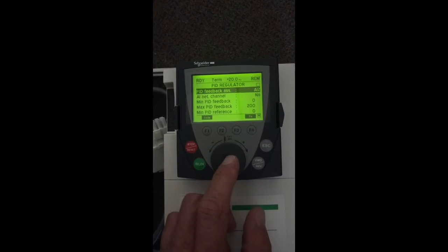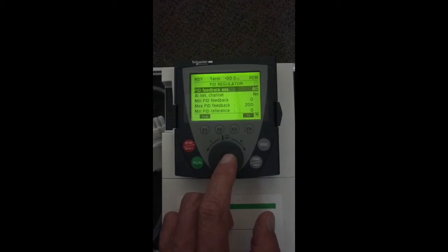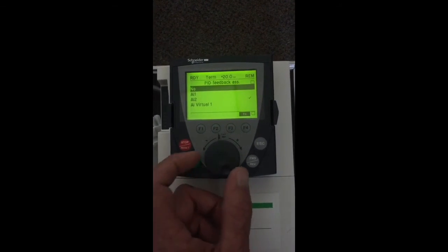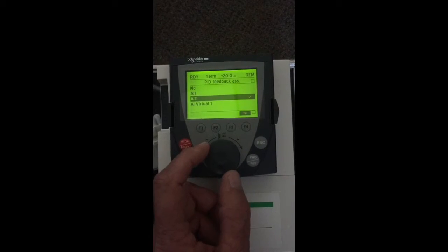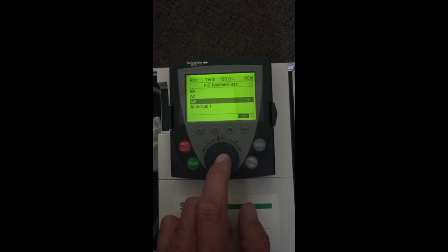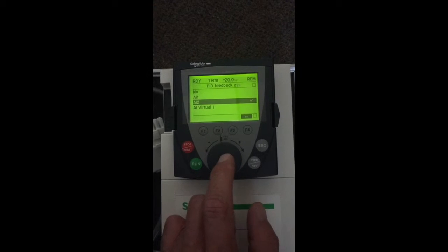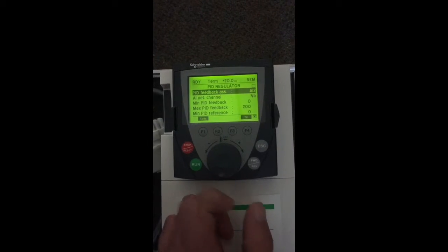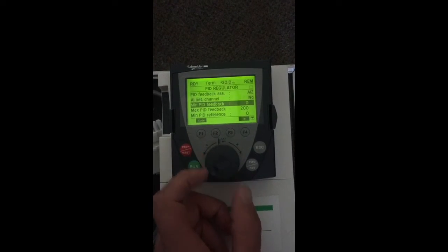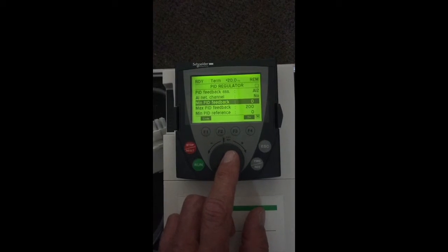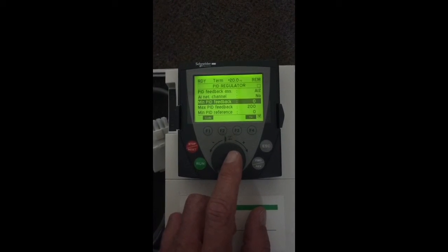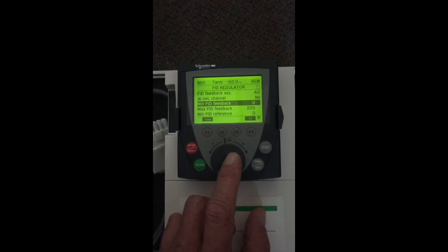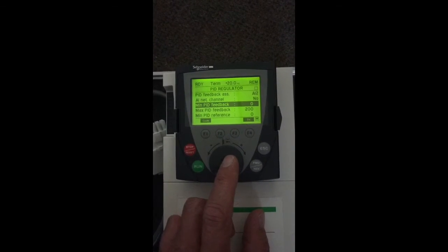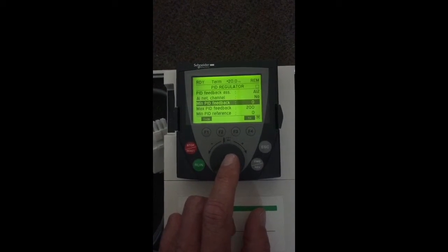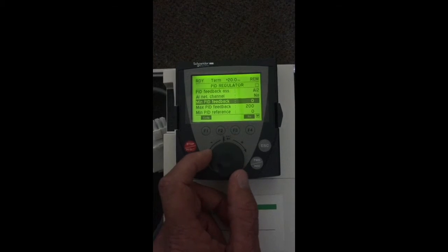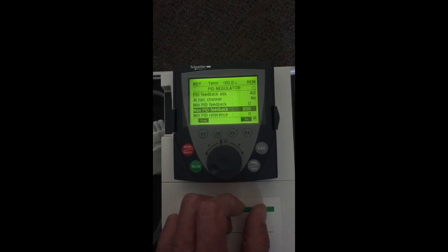You will set this for your analog input number 2. This is adjustable. You'll see that it's already set for analog 2. If not, you will adjust to that parameter. Enter it. This is the range of your temperature sensor. For this programming, I have a 0 to 200 degree Fahrenheit sensor. The minimum is 0. The maximum is 200.